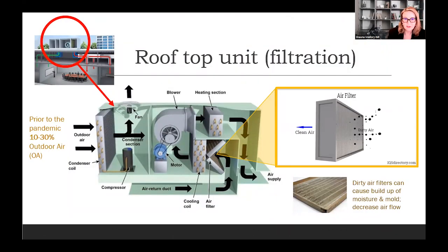If we zoom into that rooftop unit where filtration happens, it contains a filter that takes particulates out of the air, and the fineness of that filter will determine whether or not aerosols are captured before the air is recirculated. Another factor is whether the filter is maintained. Dirty air filters can cause a buildup of moisture and mold, and they can decrease airflow. And again, we're trying to cycle air through as many times as possible to replace the stale air. A dirty filter and a very fine filter can also cause something called pressure drop, which basically means that the air is not passing through the filter, and that obstruction can actually cause the unit to fail completely.